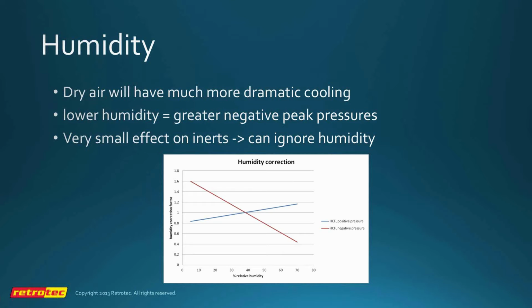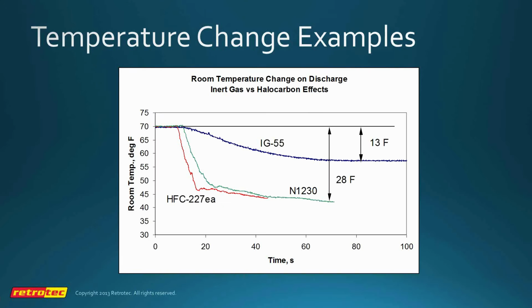primarily by the nitrogen blowdown in the tank, which is acting like a small inert agent discharge and providing a positive pressure spike. The reason why we get a negative pressure spike is that we have a huge amount of cooling that goes on in the room, which we will see in this slide here. And we see that the temperature has dropped. This is in Fahrenheit, unfortunately.